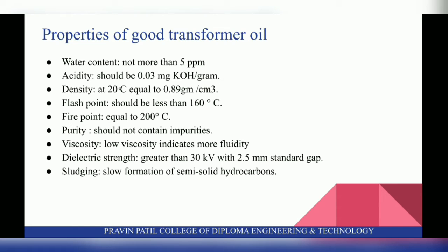So the first property is water content. The presence of moisture reduces the dielectric strength of oil. So water content should not be more than 5 ppm. Next is acidity. Acid present in the oil is very harmful. For good insulating oil, the acidity neutralization value should be 0.03 mg KOH per gram.